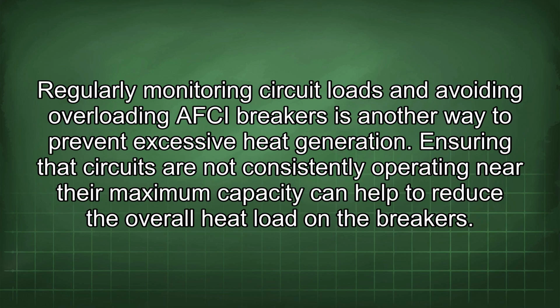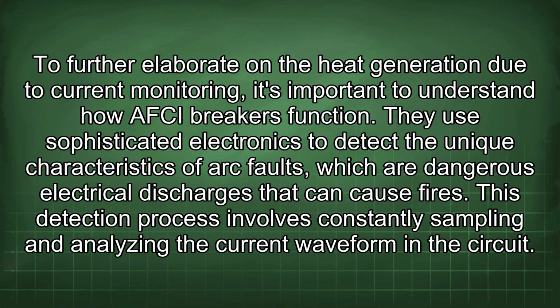Regularly monitoring circuit loads and avoiding overloading AFCI breakers is another way to prevent excessive heat generation. Ensuring that circuits are not consistently operating near their maximum capacity can help to reduce the overall heat load in the breakers. To further elaborate on the heat generation due to current monitoring, it's important to understand how AFCI breakers function. They use sophisticated electronics to detect the unique characteristics of arc faults, which are dangerous electrical discharges that can cause fires. This detection process involves constantly sampling and analyzing the current waveform in the circuit.